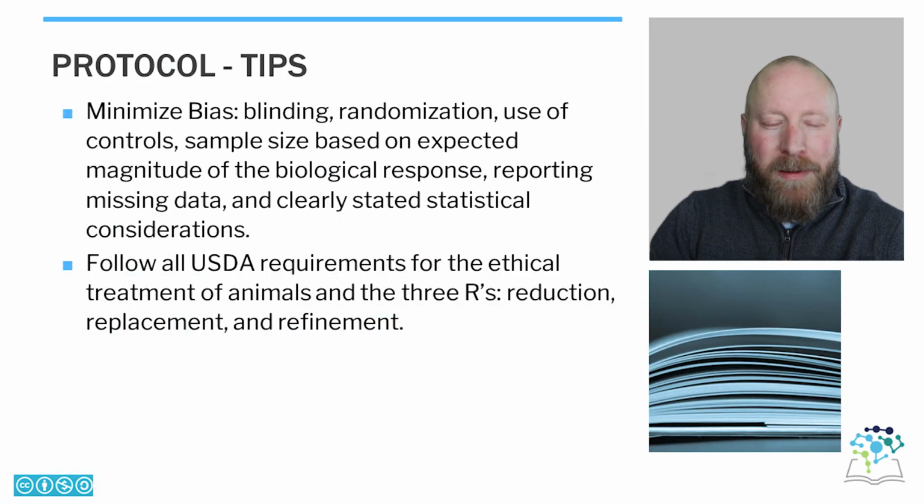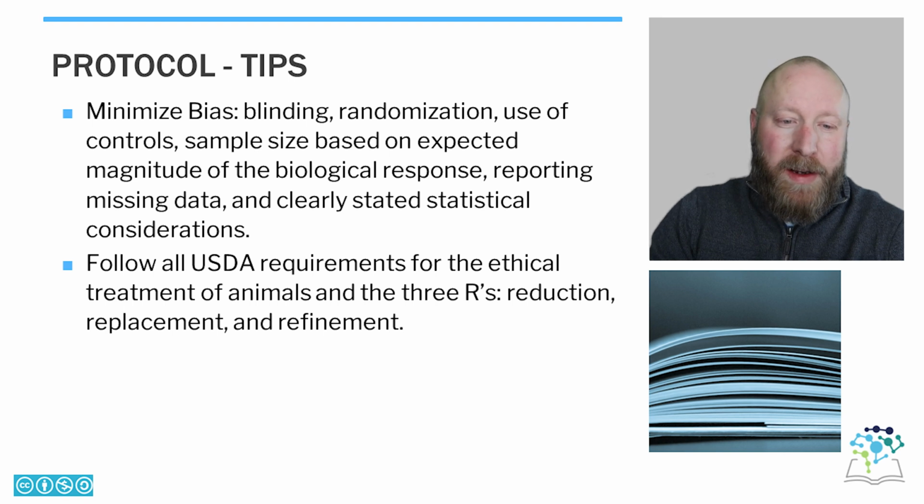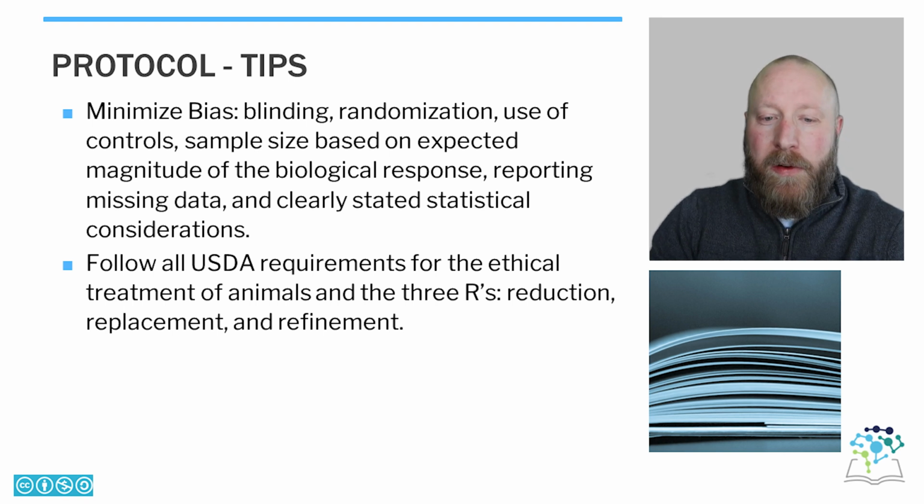A few tips for protocol. Bias control. So this is a huge thing for the FDA. In order to minimize bias, several techniques can be employed. These are my favorites that I've actually pushed for in my industry. So employee blinding, randomization of both implanting and staff, the use of control articles, appropriate sample sizing, and the biggest one is pre-declaring your statistical methods that you intend to use for the analysis and reporting. To me, this is one of the biggest and most important bias controls you can put into your study.